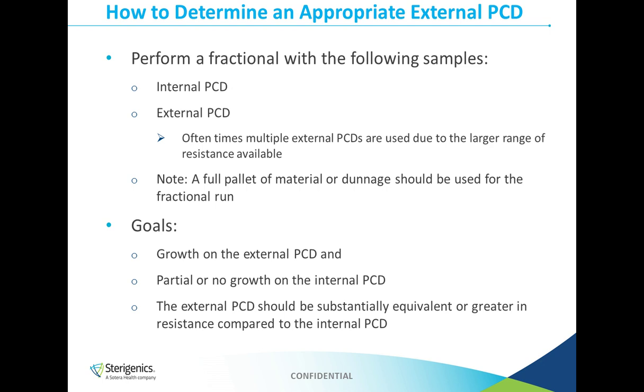And again, that external PCD needs to be equivalent or more resistant than the internal. Now when you perform these fractionals to evaluate this relationship, you should be using a full pallet of material or dunnage. The reason you're going to want to do this is because it represents what you're going to see during routine processing. If you take the device for the internal PCD and the device for the external PCD and just place them next to each other inside of a chamber, they're not seeing the same conditions that they would during routine processing, where that internal PCD would be inside the product and the external PCD on the outside. That change in where they're placed will change the characteristics and the resistance of those devices. So it's important to use that full pallet of material or dunnage for this comparison.